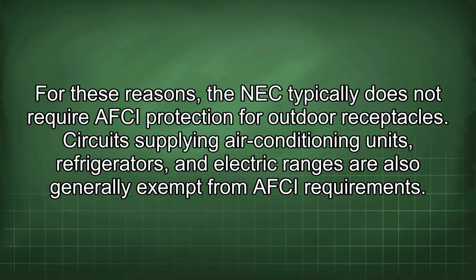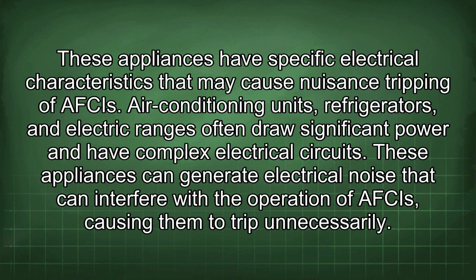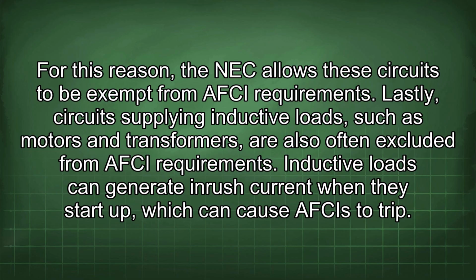Circuits supplying air conditioning units, refrigerators, and electric ranges are also generally exempt from AFCI requirements. These appliances have specific electrical characteristics that may cause nuisance tripping of AFCIs. Air conditioning units, refrigerators, and electric ranges often draw significant power and have complex electrical circuits. These appliances can generate electrical noise that can interfere with the operation of AFCIs, causing them to trip unnecessarily. For this reason, the NEC allows these circuits to be exempt from AFCI requirements.